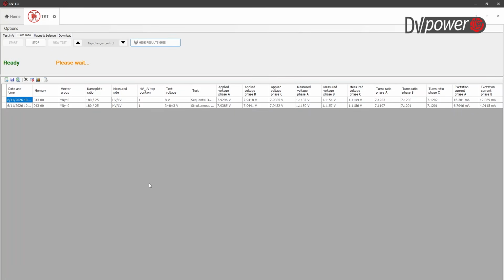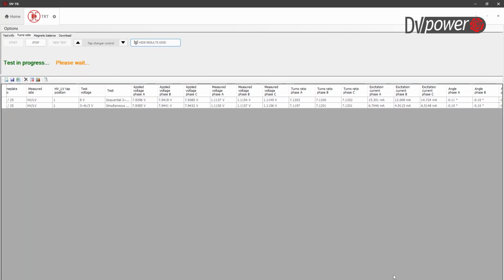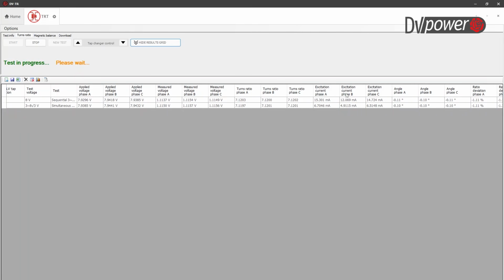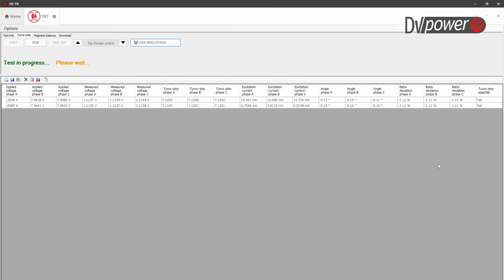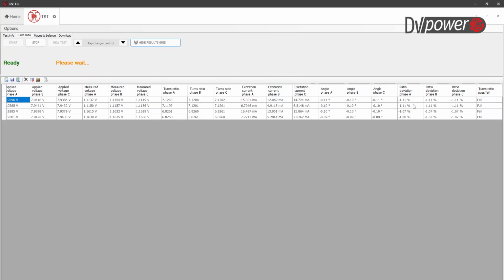Results which are displayed are here. There is a memory location, vector group, nameplate ratio, test voltage, applied voltage, measured voltage, and information about excitation current, phase angle for each phase, deviation for every phase, and pass-fail assessment.